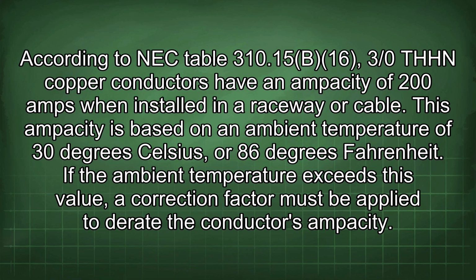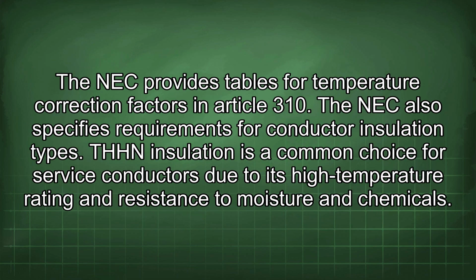310.15(B)(16), 3/0 THHN copper conductors have an ampacity of 200 amps when installed in a raceway or cable. This ampacity is based on an ambient temperature of 30 degrees Celsius or 86 degrees Fahrenheit. If the ambient temperature exceeds this value, a correction factor must be applied to derate the conductor's ampacity. The NEC provides tables for temperature correction factors in Article 310.